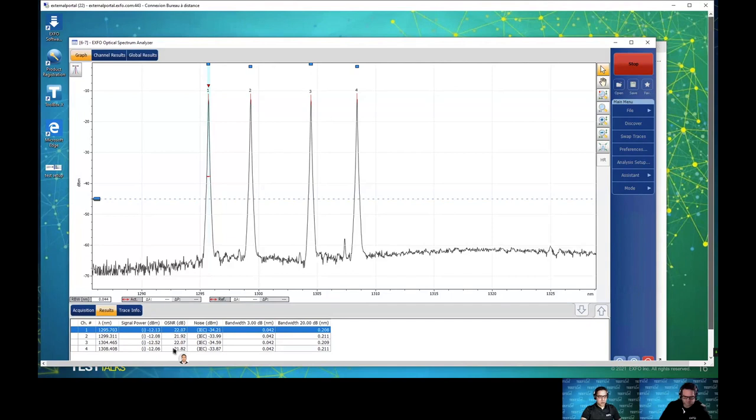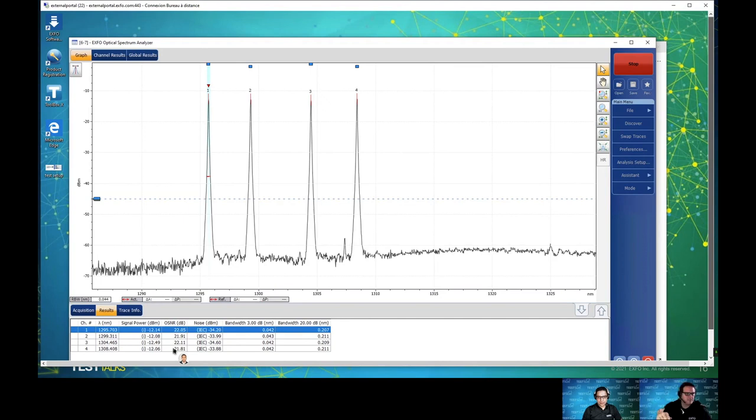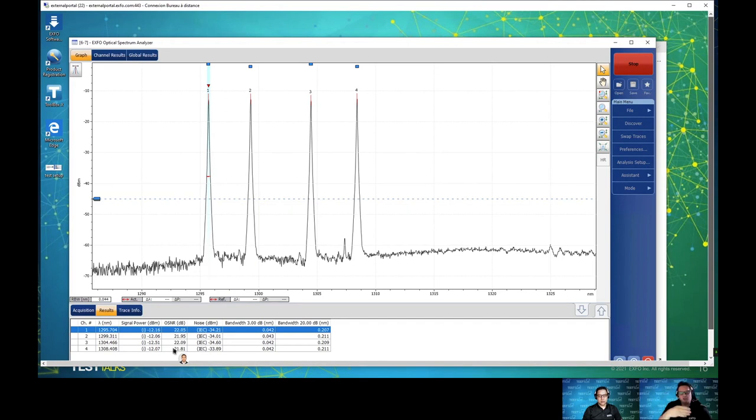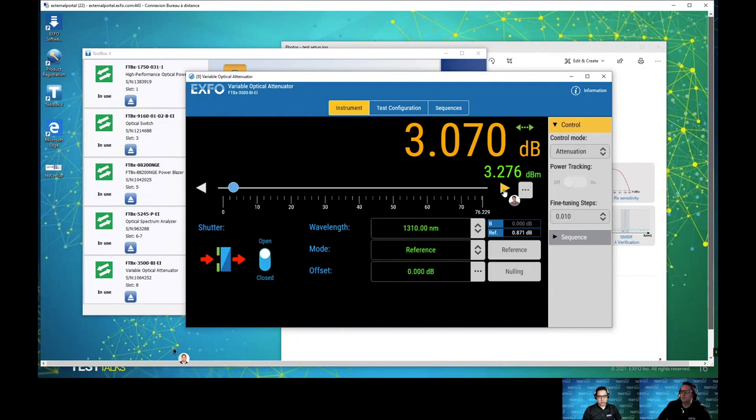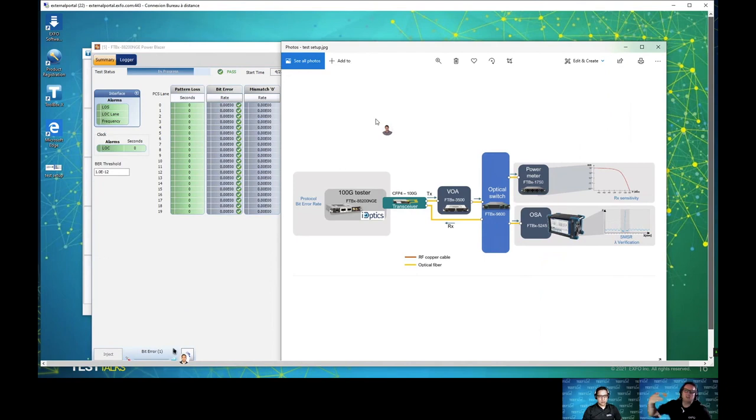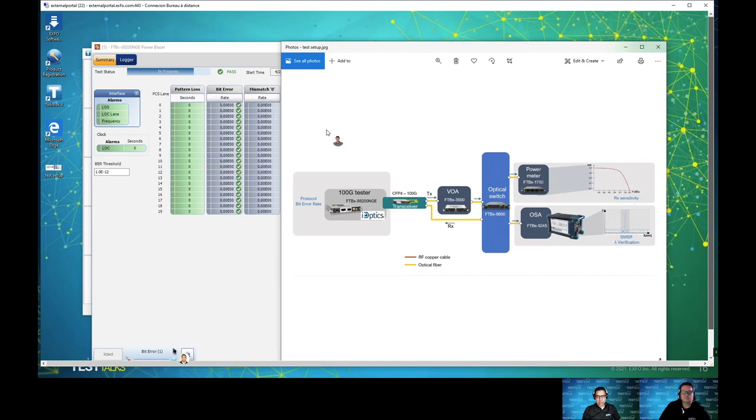That's it for the optical testing. So if you have any question, please feel free to ask. I don't know if someone in the audience have any question related with the different tests that we have performed. I'd be interested, could you replace a wave meter with the OSA? Yeah, absolutely. Well, it depends. As I said before, I was verifying the lambda using the optical spectrum analyzers. But to do that, we need to make sure that the optical spectrum analyzer has a very high accuracy, wavelength accuracy. In this case, if the OSA is, I don't know, plus or minus 10 picometers of accuracy for the lambda, in that case we can replace the wave meter. So instead to have two different equipments in the production line, we're going to have only the OSA, which allows to reduce the CAPEX and the OPEX.